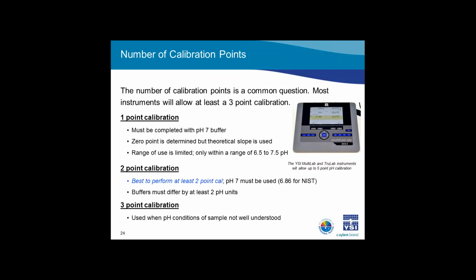More common and most recommended is to conduct a 2- or 3-point calibration. I suggest doing a 2-point calibration if you know which side of the pH scale you expect to measure in. For example, if you know you are going to be measuring acidic samples, it is only required to calibrate at 7 and 4. In this example, calibrating at 10 will not improve your readings below 7. If you're not sure which side of the pH scale you will be measuring, then perform a 3-point calibration at 4, 7, and 10. Some meters allow you to calibrate up to 7 points for pH. Just make sure that you calibrate at buffer 7 for one of them, and that a second buffer differs by at least 2 pH units from the 7 in order to establish a good practical slope.